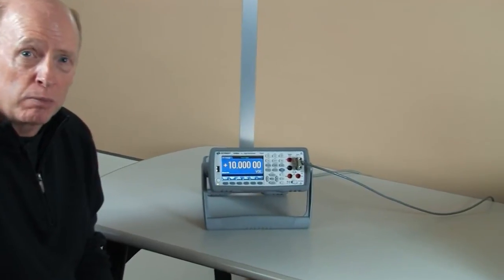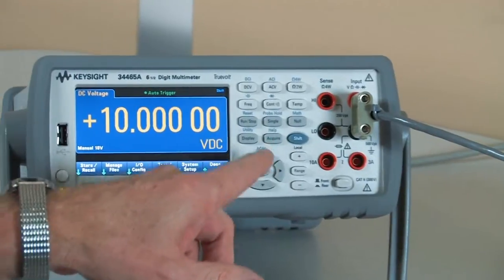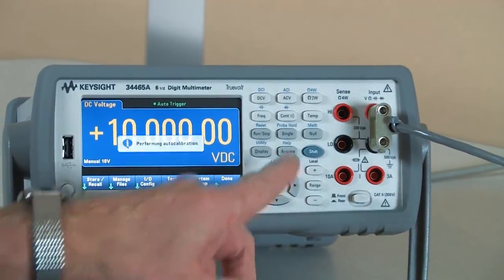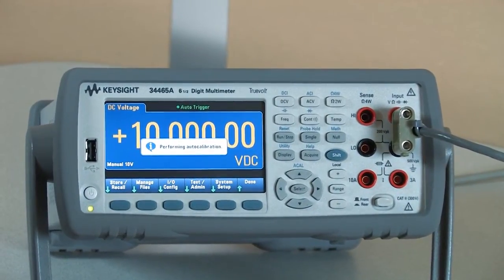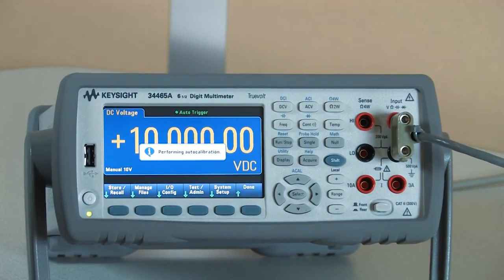To perform an auto calibration, you simply press the shift key followed by the up arrow key which starts the auto calibration. The auto calibration takes approximately 15 seconds to complete and in most cases the input signal can remain applied.